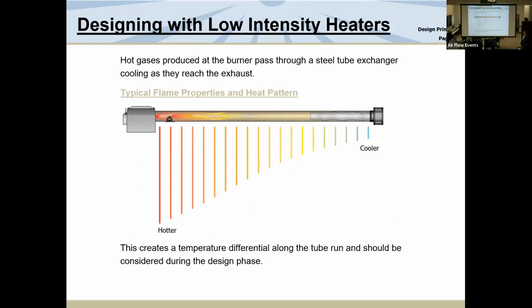Next slide. Okay, we talked about this. I think this is really important. I want this really stuck in your head: hot end and cold end. You get that call 2 or 3 times a week from a customer about why it's hot end and cold end. All right. For us to vent a heater, the standards require us to be less than 480 degrees. So everything on the end of the heater is based upon our certification, which is a minimum of 232 degrees and a maximum of 480. What is 232 Fahrenheit?